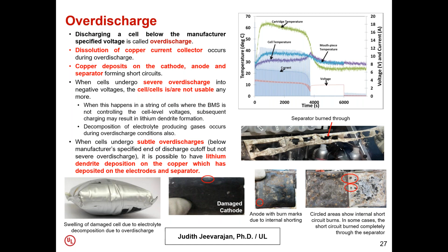So the takeaway from this is that over discharge or under voltage protection is absolutely needed at the cell and battery level for all applications. And if you do stringent cell screening and matching, you can avoid deviations in voltage between the cells, thus preventing any one cell from going into lower voltage than the others or into an overdischarge condition. Cell balancing also helps with this, keeping the cells balanced within a small delta voltage value.